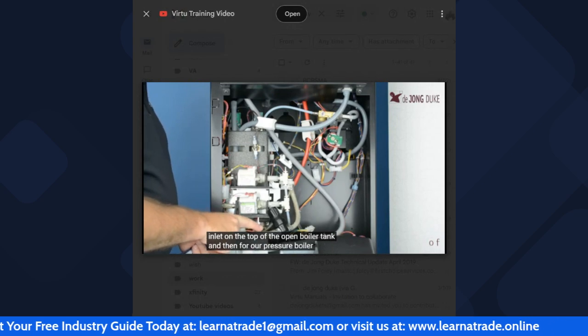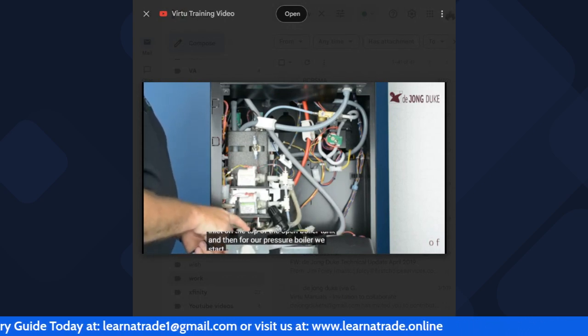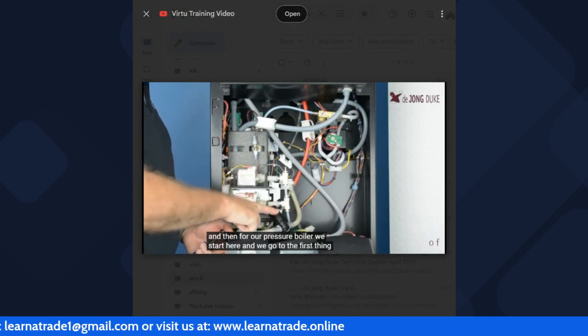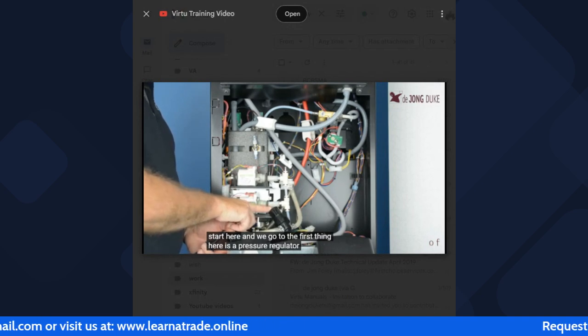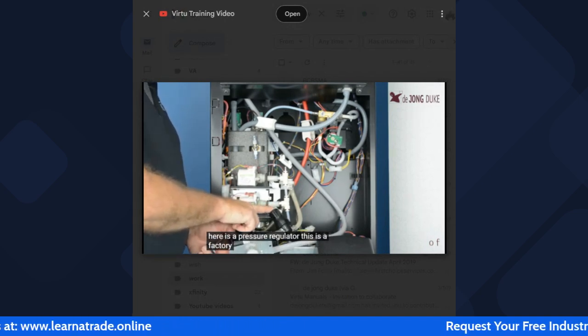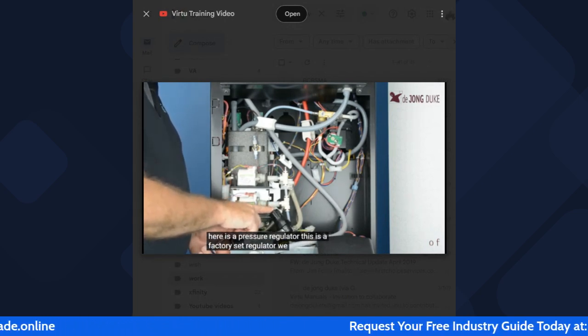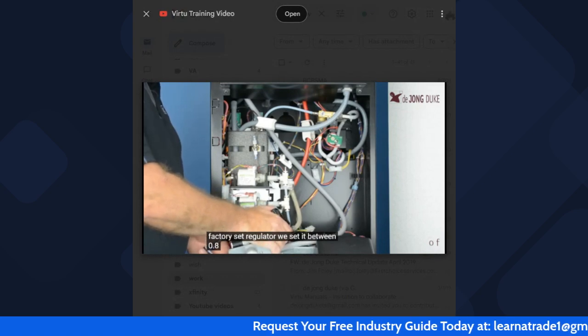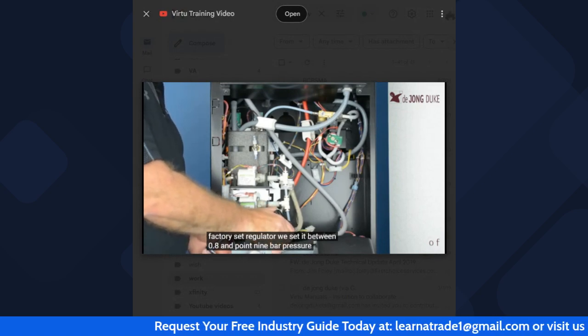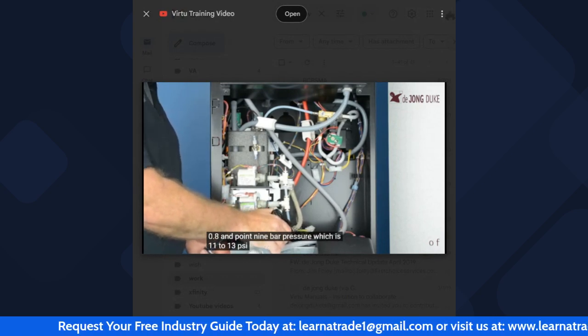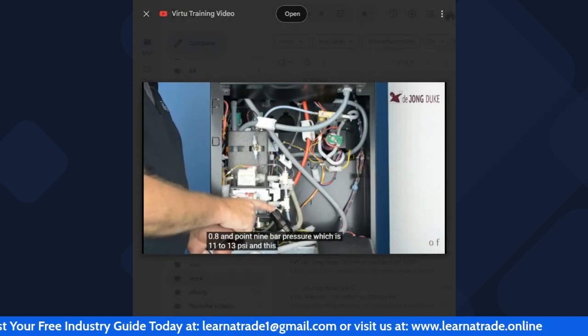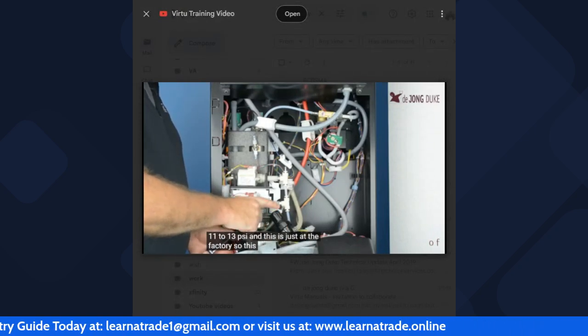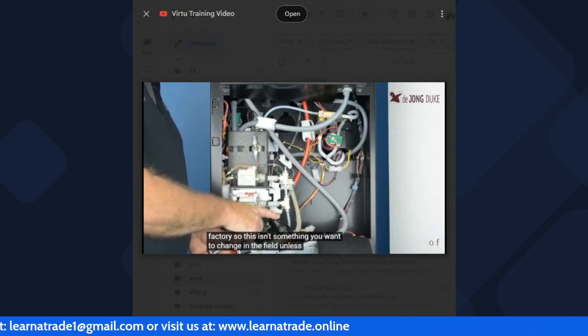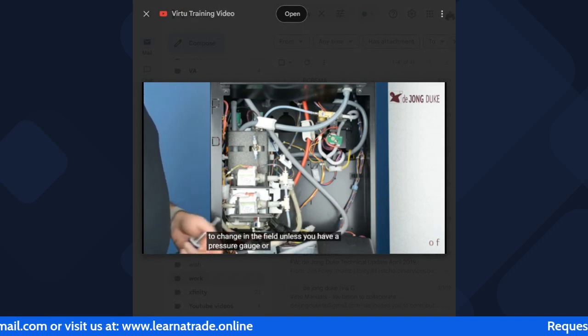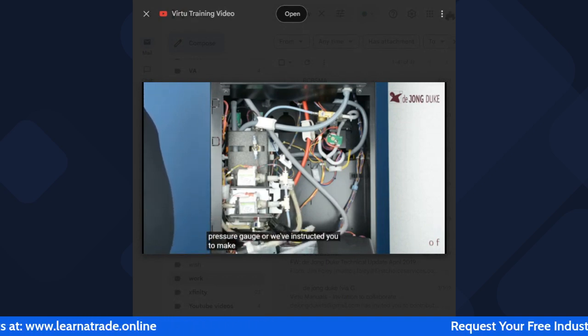And then for our pressure boiler, we start here and the first thing we come to is a pressure regulator. This is a factory set regulator. We set it between 0.8 and 0.9 bar pressure, which is 11 to 13 psi. And this is adjusted at the factory, so this isn't something you want to change in the field unless you have a pressure gauge or we've instructed you to make that change.